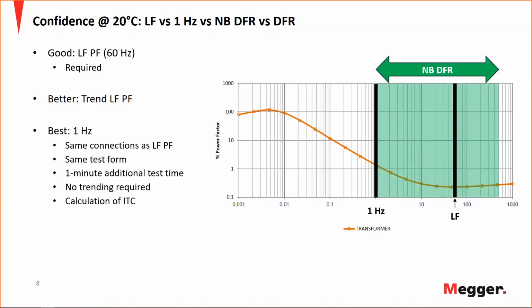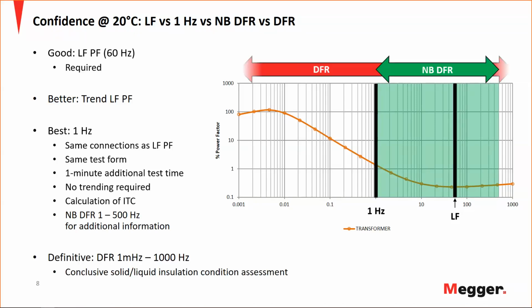In addition to the 1 Hertz, you may have also heard the term narrowband DFR. It's just a little bit of an expanded range from 1 to 500 Hertz, where you can get some additional information. But if you really want to know the exact state of the insulation that you're testing, you must do a DFR IDAX test. This is the only one that's going to give you that conclusive solid or liquid insulation condition assessment. But if you don't have the IDAX and you are doing line frequency power factor today, how can you improve your evaluation? That will be testing at 1 Hertz. And now I have a few examples of exactly how testing at 1 Hertz helps you confirm good measurements, validate questionable measurements, and then finally detect deteriorating insulation when line frequency power factor looks good.